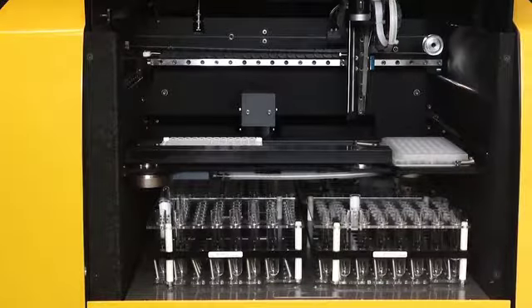We do have a pre-dilution plate if it is required. We can dilute 1 to 30,000 if need be, but most tests don't need to go that high. But if that feature is needed, we can do that in the pre-dilution plate.